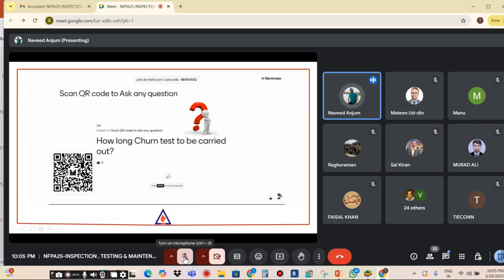So let me answer one question. Basically, it's how long the churn test is to be carried out. Churn test is basically every week we have to check the system with a no flow test. We call churn test a no flow test. For an electric pump it's 10 minutes and for a diesel pump it's 30 minutes. Next is how many years once the pipe internal condition needs to be checked. Every year you have to check the piping internal condition, but it also depends upon your water quality. If you are living in an area near the sea, then maybe the interval can be 6 months, but you have to check it every year.